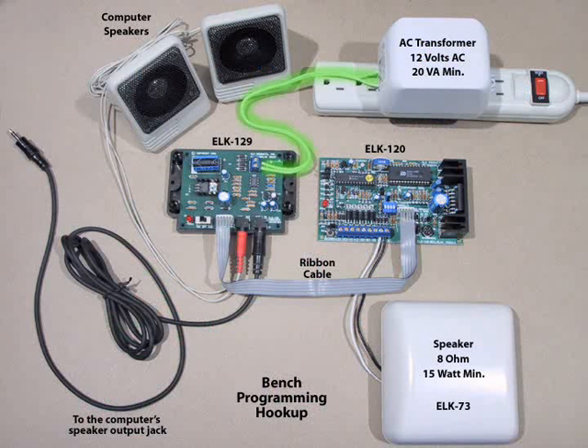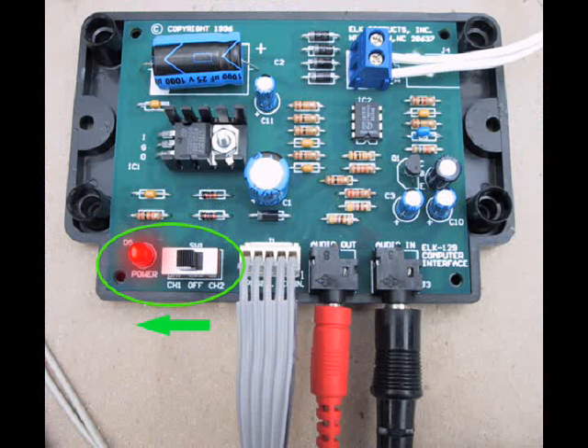Connect a 12-volt 20VA minimum AC step-down transformer to the AC terminals on the ELK 129, located under the cover. Then plug the transformer into an AC receptacle. To confirm the power connection to the ELK 129, move the SW1 power switch to CH1 and look for the power LED on.